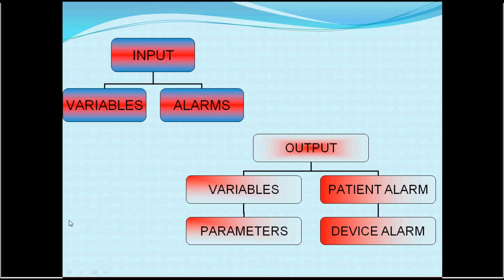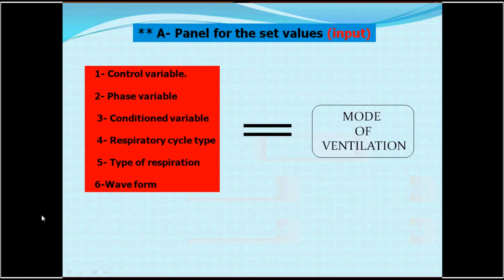Looking at the panel for set values, the mode is a constellation of control variables, phase variables, conditions, breath types, and waveforms. You select certain combinations of these to define your mode of ventilation.